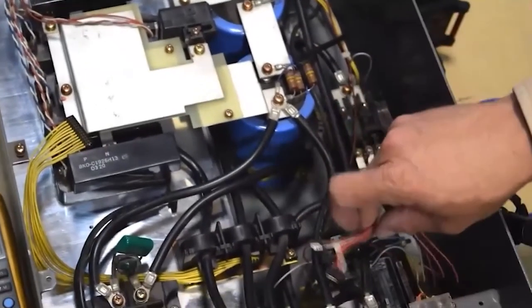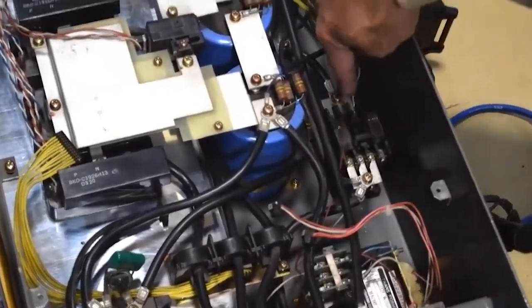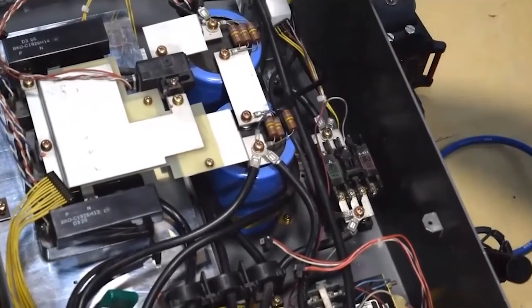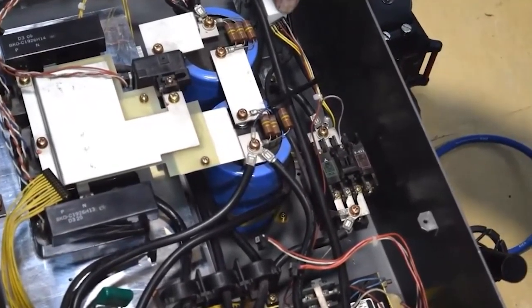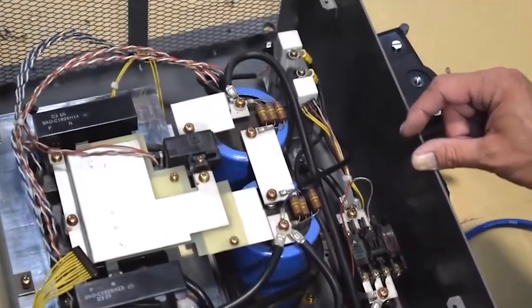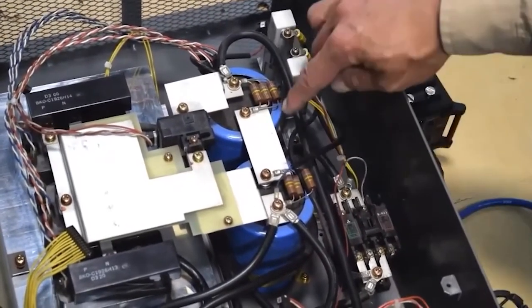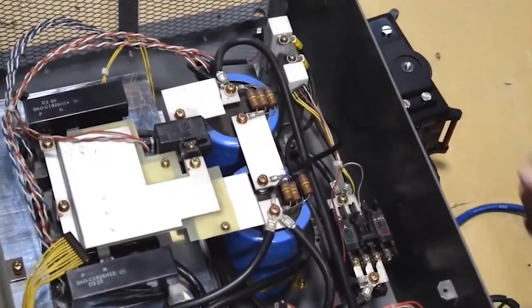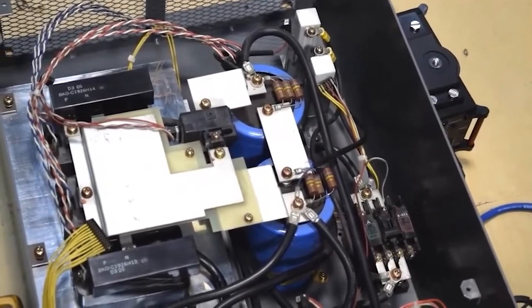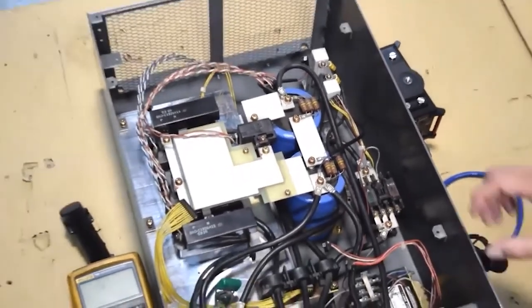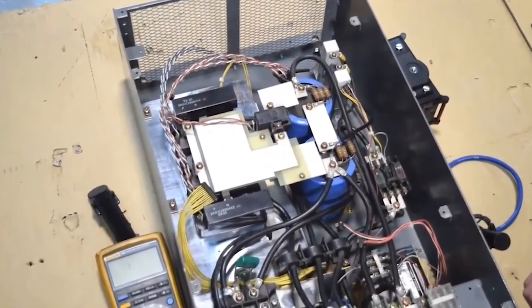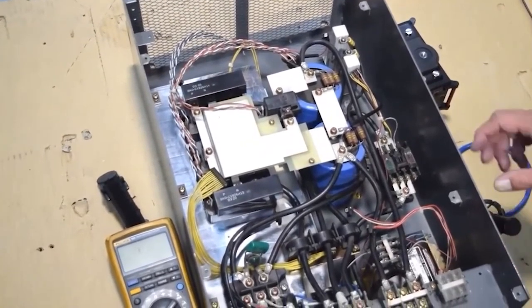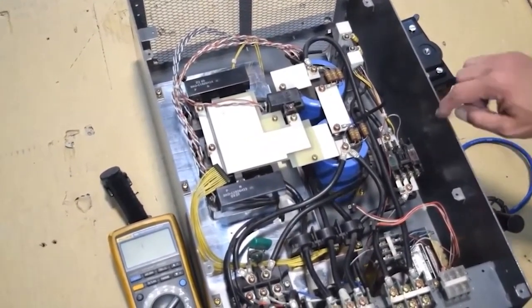Then moving along, we've got our pre-charge circuit, which is over on the right-hand side. You can see a contactor in this case, and it's going to be in parallel with some resistors, which are more up towards the top of it. This is designed to slow the rate of charge to the capacitors, just like we talked about earlier, so we don't hit the capacitors with all that voltage at the same time, which normally will cause a failure.